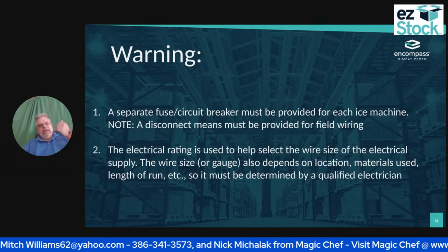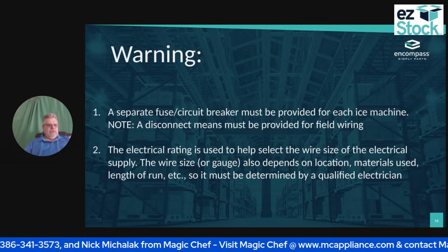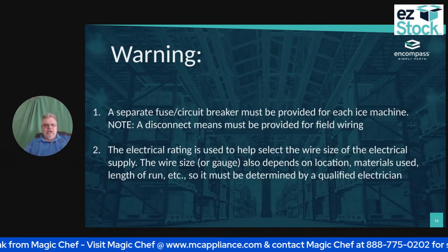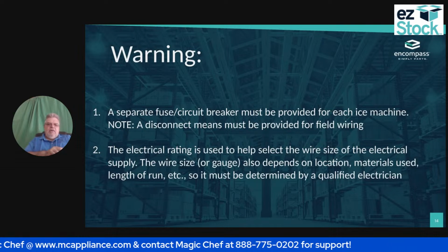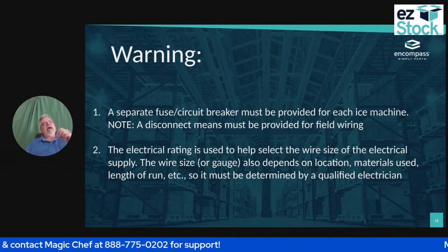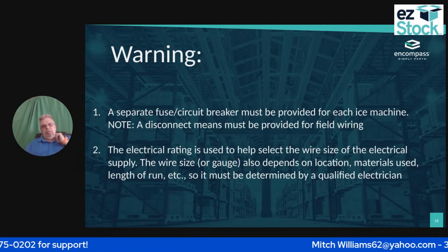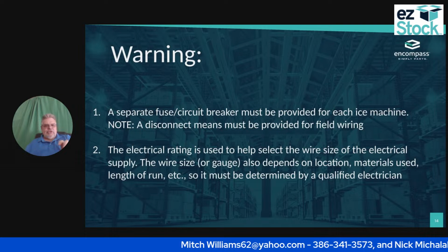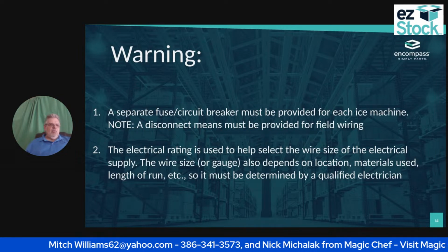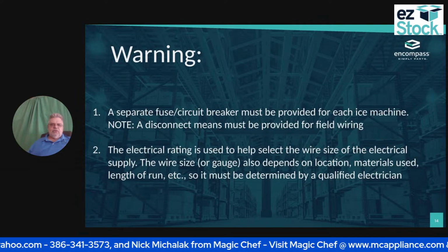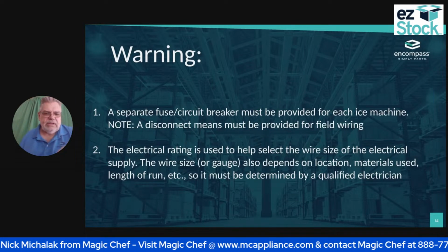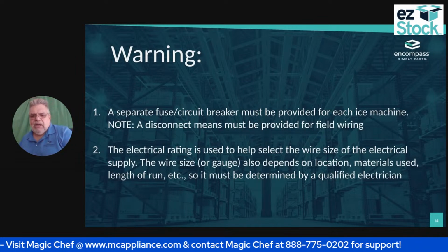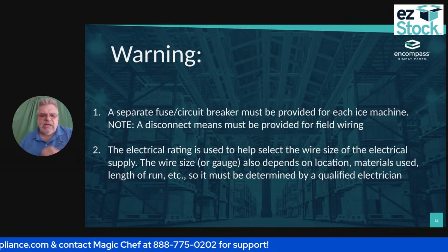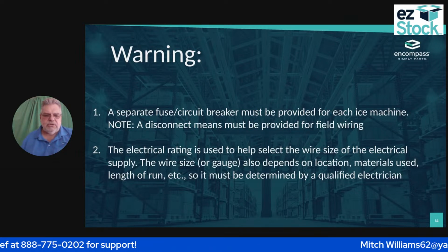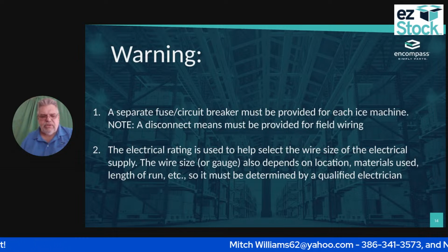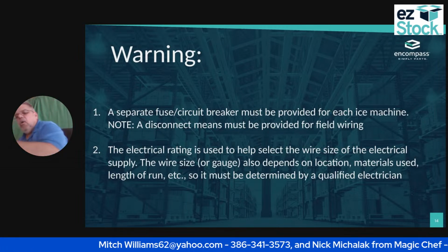The other thing, it has to be on a separate fuse or circuit breaker, provided for each ice machine. A disconnect must be provided for field wiring, so that I can either flip the breaker or unplug it. That's something the electrician should do. You as a technician should not be wiring anything unless you're a certified electrical person. The electrical rating is used to determine the wire size of the electrical supply. The wire size or gauge also depends on the location, the materials used, the length of the run, and all kinds of other things, so it has to be determined by a qualified electrician.